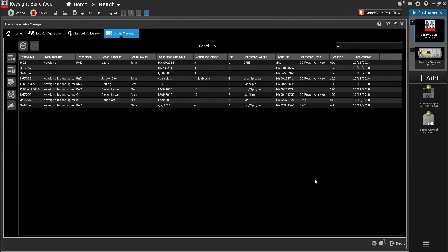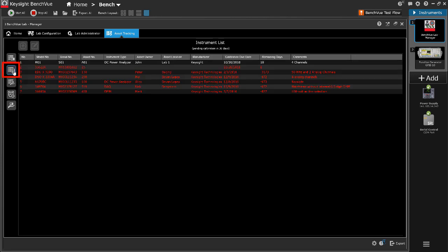To view the list of instruments currently with calibration due date lapse, click the Pending Calibration Asset icon. The remaining days information in negative value indicates the number of days that has lapsed since the calibration due date.